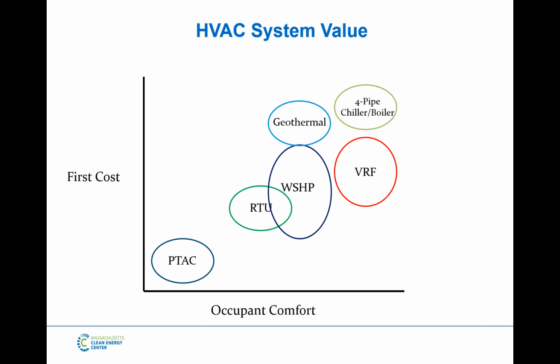The first thing we're looking at here is the first cost, and along the bottom side here is occupant comfort. So if we look at our two extremes, the traditional extremes of the HVAC industry, the most inexpensive and least comfortable, least efficient option would be PTACs, packaged terminal air conditioning units. These are essentially just permanently installed window units. And although I say permanently installed, they're window units that are usually put in a sleeve in the, JS calls it the highway motel. I agree with that. And they typically last about 5 to 6 years.